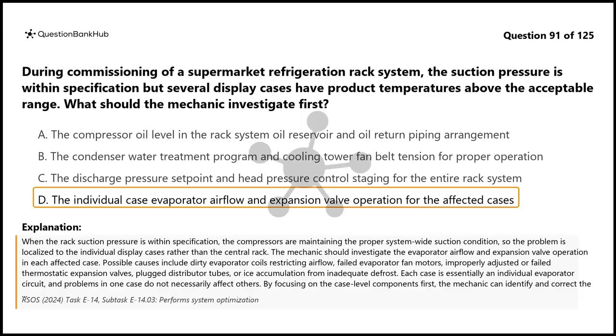Possible causes include dirty evaporator coils restricting airflow, failed evaporator fan motors, improperly adjusted or failed thermostatic expansion valves, plugged distributor tubes, or ice accumulation from inadequate defrost. Each case is essentially an individual evaporator circuit, and problems in one case do not necessarily affect others. By focusing on the case-level components first, the mechanic can identify and correct the specific cause without making unnecessary changes to the central rack system.